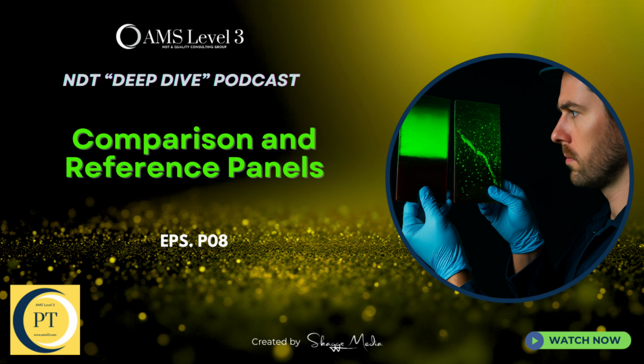Okay, let's shift gears a bit towards actual measurement, getting quantitative. But before the fancy panels, we need to talk about developers. They play a huge role, don't they? Oh, massive. Especially when you're inspecting opaque parts where you can't see the penetrant inside the crack. Developers boost the indication brightness in, well, basically three ways. One, they draw the penetrant out, increasing the effective thickness you're looking at.